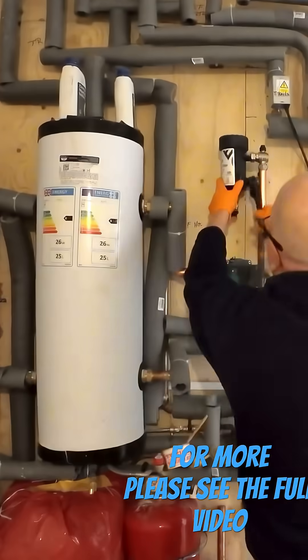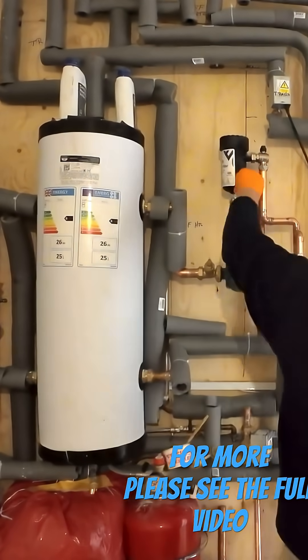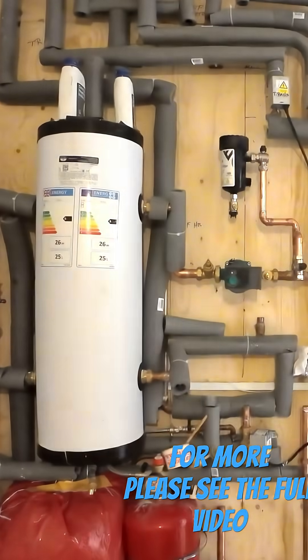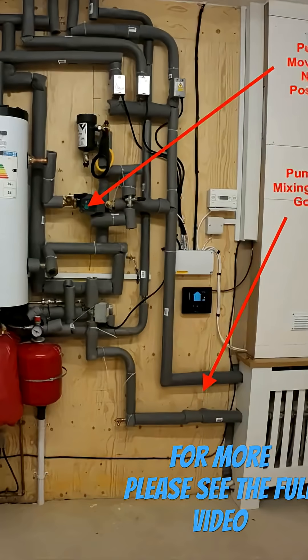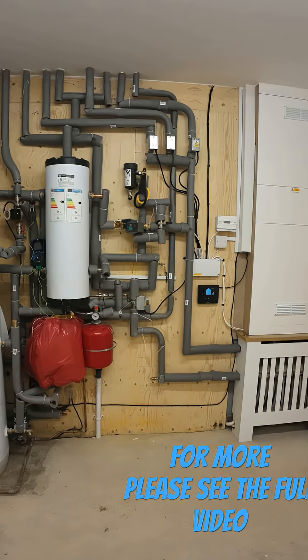These are just a few speeded-up clips of me actually making the alterations. The reason I'm making these alterations is because, if you take a look at one of my previous videos, when I initially commissioned this system, everything seemed to be working just fine. But after a while, I thought the heat pump was frosting up a little bit too regularly for my liking. So after receiving a few helpful comments and some research on this matter, this is the action that I decided to take.